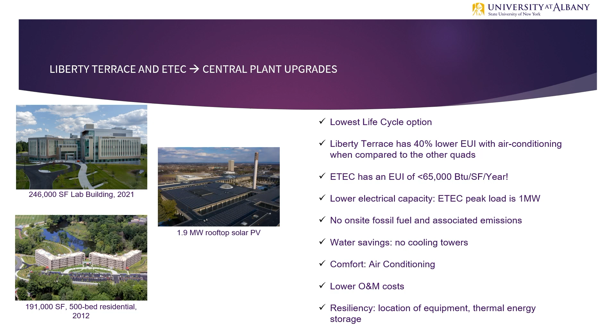So again, it provides a lot of opportunity for us to diversify, have a more resilient, redundant system on campus. So I'll end with some of the lessons that we have learned through these 2 projects that we already have and the third major one that we're undergoing right now. Do not forget about heat of compression. I know we're in a region which is heating dominated, right? But with the heat pumps, when you're rejecting heat in the summertime, you're also rejecting that heat of compression. So do not forget that, because even Liberty Terrace, which is a residential building, we are rejecting more heat into the ground than we are extracting on an annual basis. Because we had data, we were able to show that.